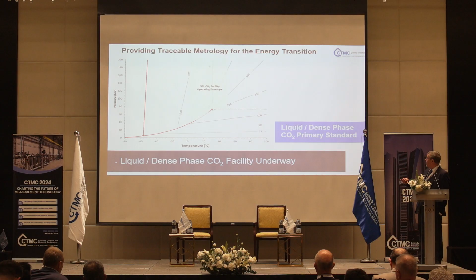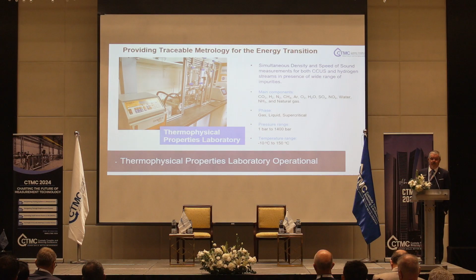As I mentioned earlier, carbon dioxide for CCUS is not just carbon dioxide. It's many, many components. So we're building a thermophysical properties laboratory. We have built it, it is operational, and it's designed to allow us to calculate density and speed of sound measurements for both CCUS streams and hydrogen streams. So the typical components, obviously, are CO2 and hydrogen, but we can also introduce nitrogen, methane, argon, water, NOx, SOx, ammonia, all the things that we understand will be part of CCUS carbon dioxide. It will cover the gas, the liquid, and the supercritical phases. And because of that, it has a large pressure range up to 1400 bar, and it goes from pretty chilly to pretty hot. And we think that will cover most of the needs of our customers and the industry.